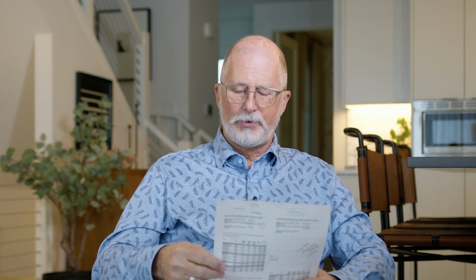So if I take those windows and want to make the solar heat gain low enough, I'd have to reduce them down to a 0.21 solar heat gain. I don't think they make a 0.21 solar heat gain in a triple glazed window, so that doesn't work - we can't make that work. I either have to reduce the amount of windows or find a window that currently isn't even in production. So that's where the challenge is.